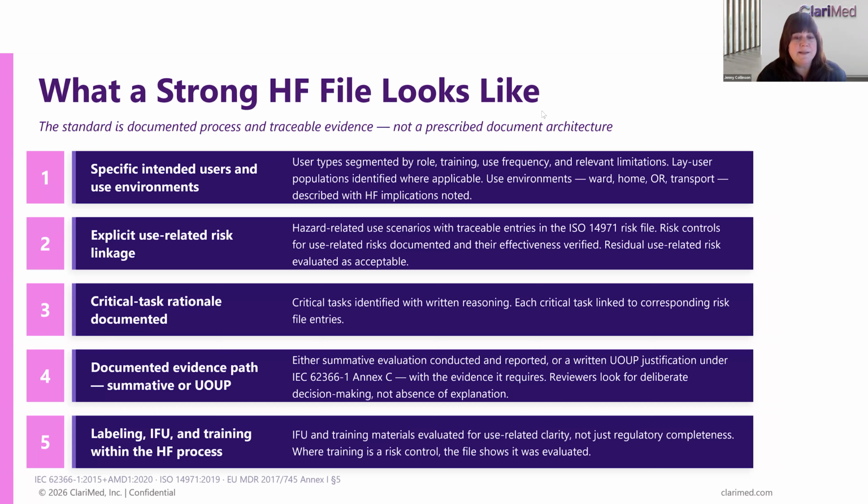The next one is that it is expected that the usability engineering file is linked to the risk file. And the risk file drives and determines hazard-related use scenarios. It drives any user interface mitigations and how they will be evaluated, and also links back the documentation of any evaluation. And then, of course, there needs to be a determination of acceptability.